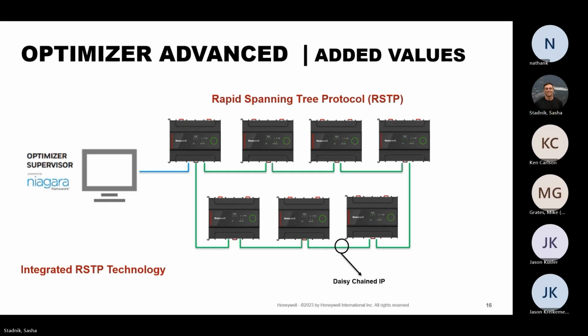On a loop, you have a circle, like the one that is there. And what happens if in a circle I lose one of the cables? Well, it can go the other way. In an MSTP daisy chain topology, if I lose one trunk, this token cannot continue - that is why you don't see the rest of the controllers from that point and beyond. But in a circle, I can go all the way, and that is what it's called self-healing.